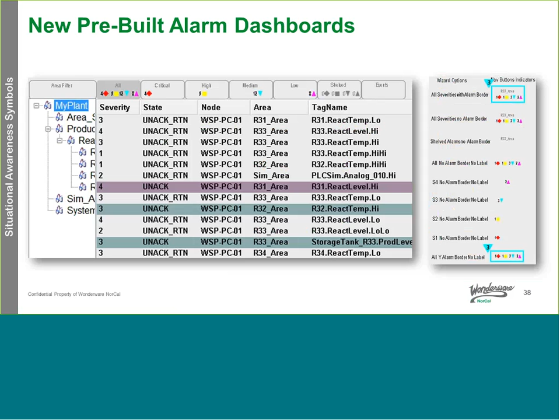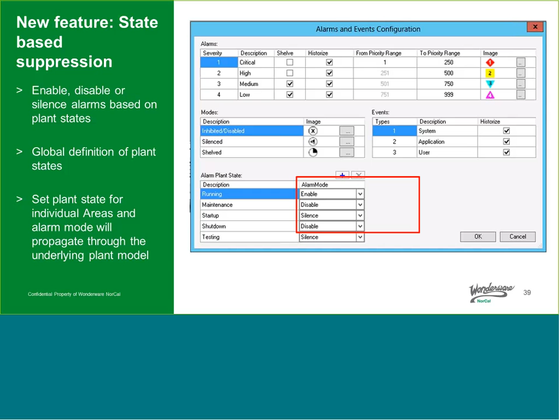We also have what's called state-based suppression. So if you're a given area of your plant, if it's in maintenance, if it's in startup, if it's in testing, you can silence or disable those alarms. So again, you're not getting those alarm floods that really can make your operator miss the important alarms that they do need to be paying attention to. So the ability to turn off alarms by area of the plant is a very useful alarm management tool. Alarm shelving is another useful tool that allows you to basically put alarms on snooze.